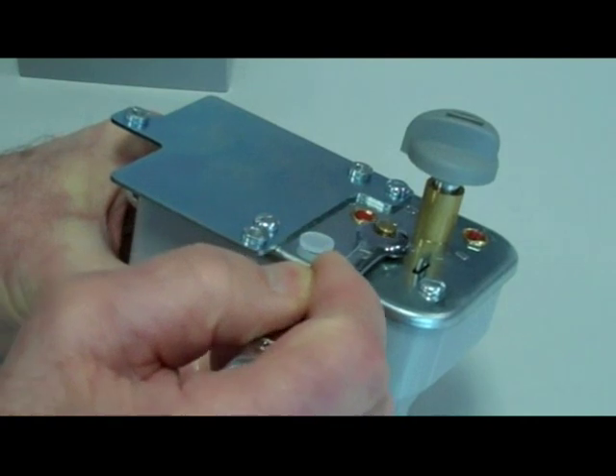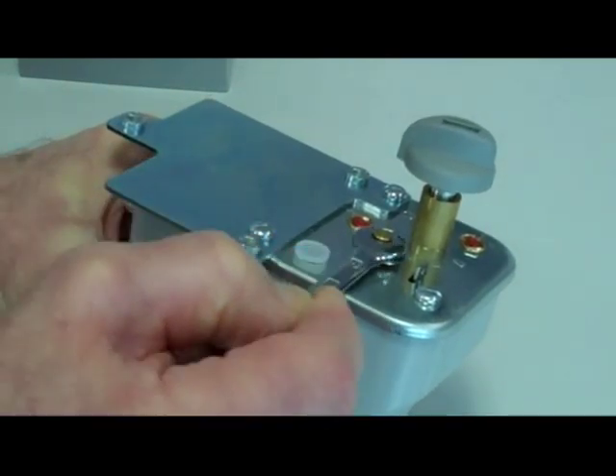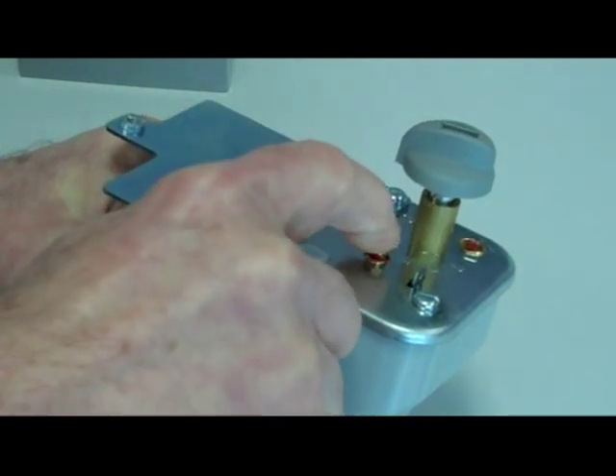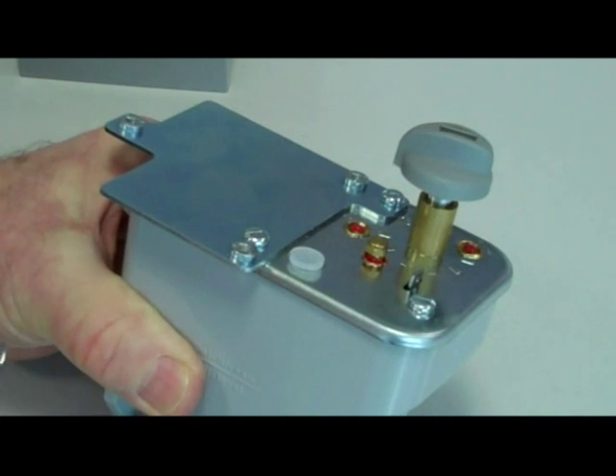Then screw the hexagon nut anti-clockwise, moving the nut upwards very carefully until there is no movement of the thermostat pin. Please ensure not to go past the position where movement of the thermostat pin first stops.